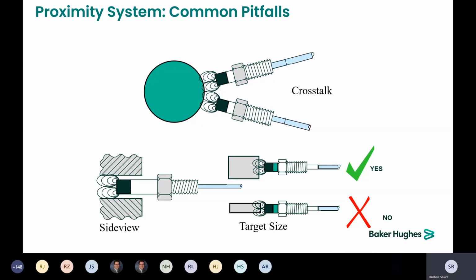One other thing that I've seen people do is run the probe all the way down till it touches the shaft, feeling for that extra tightness as they roll it down. And that can lead to cracking of the tip, which damages the antenna, allows oil ingression, things like that that just destroy the probe. So again, we recommend you just roll it down to a -2 volts and then back it out to your proper gap setting. You also need to make sure that you have an appropriate target size.